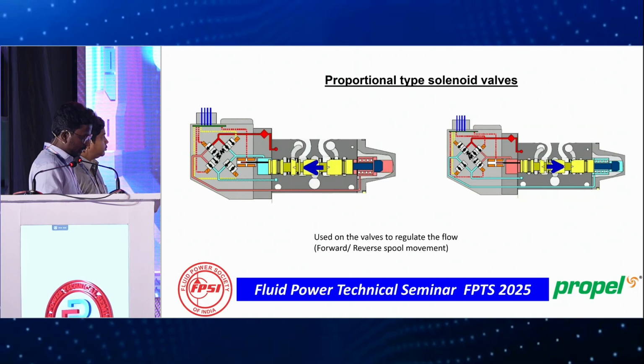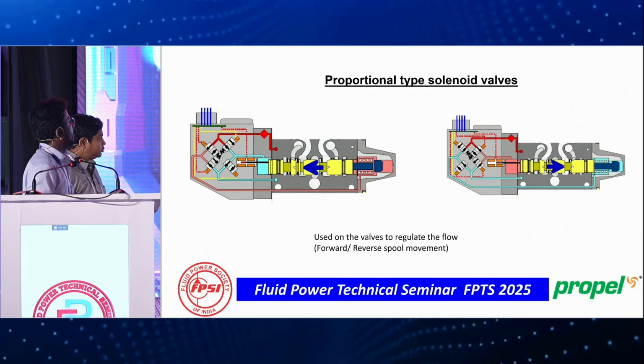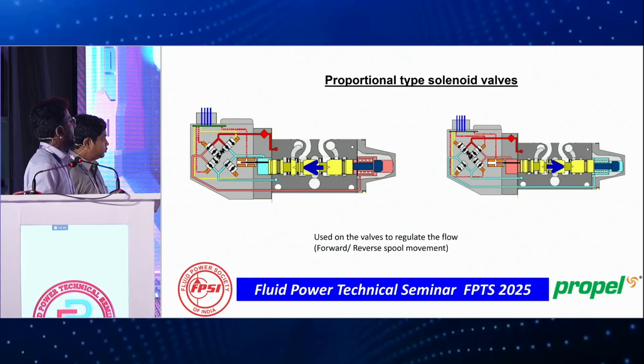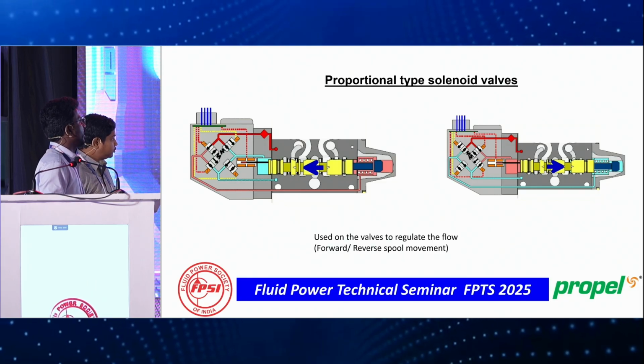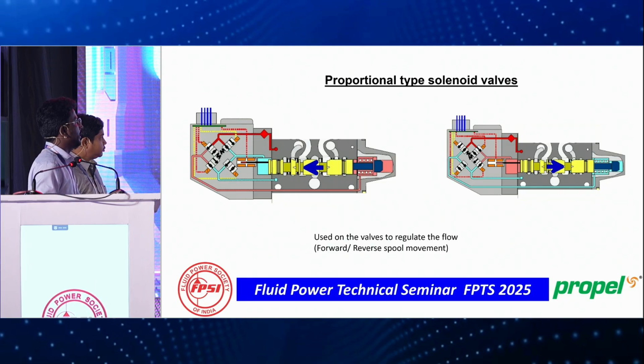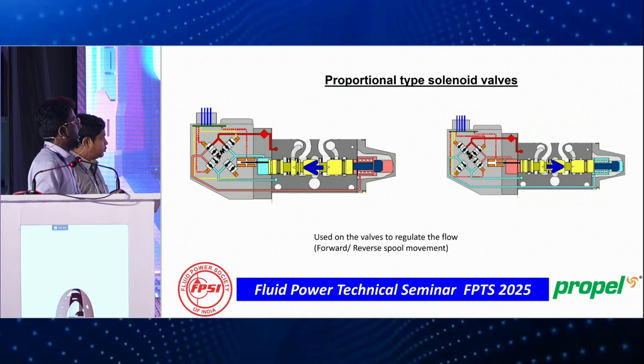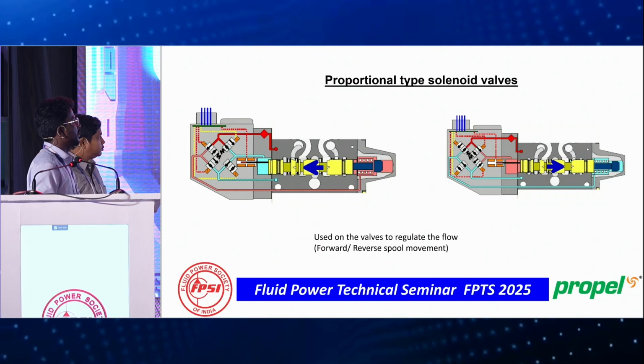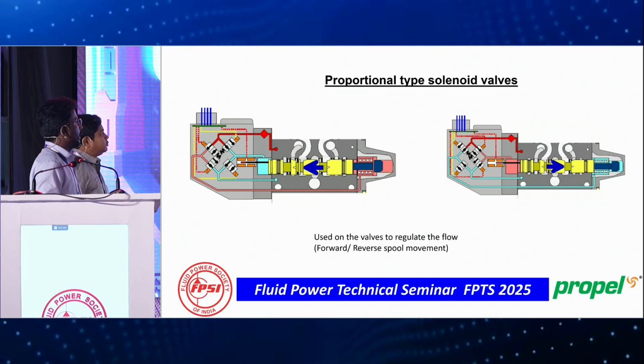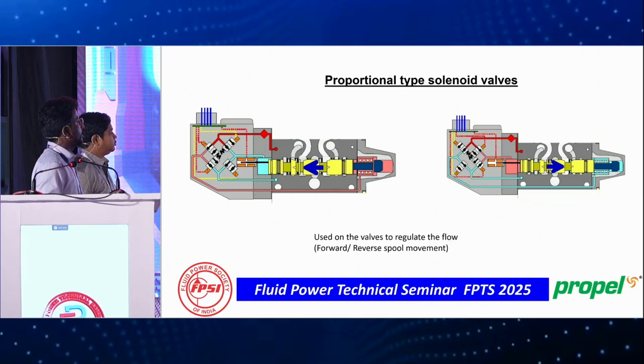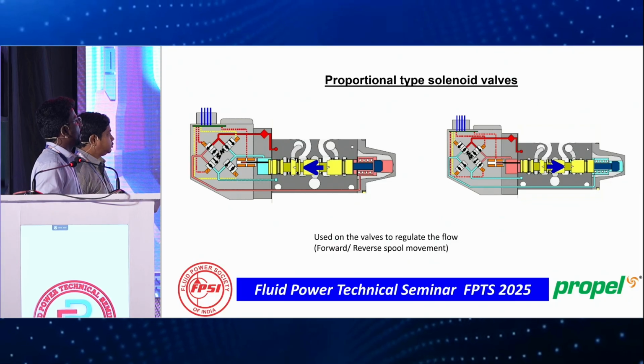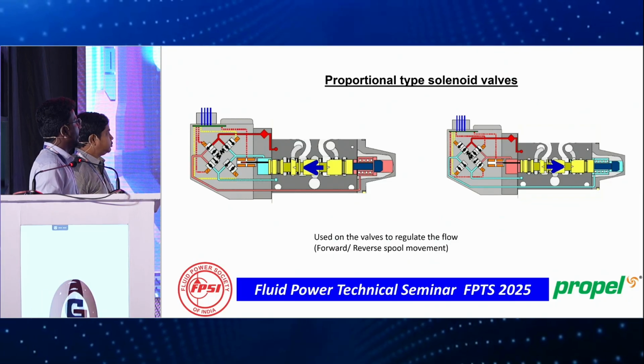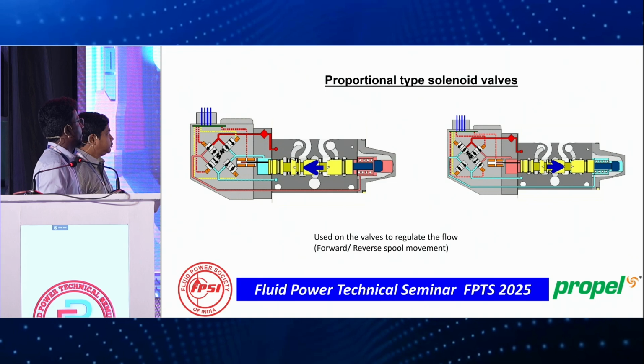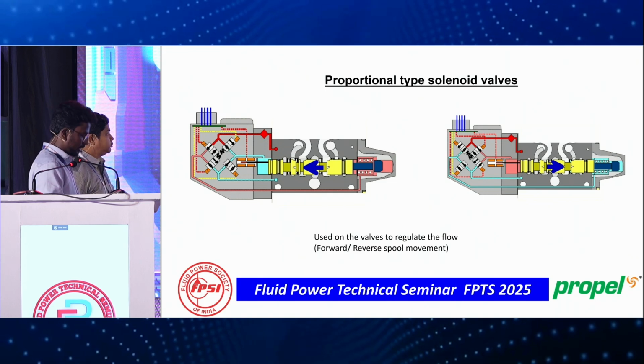But typically, proportional solenoid valves have the advantage of LVDT, which provides feedback to the master spool, indicating whether it is located on the A side or B side. Based upon that, the master spool moves from one position to another position. To move the master spool, we can vary the electrical current from this electrical section.